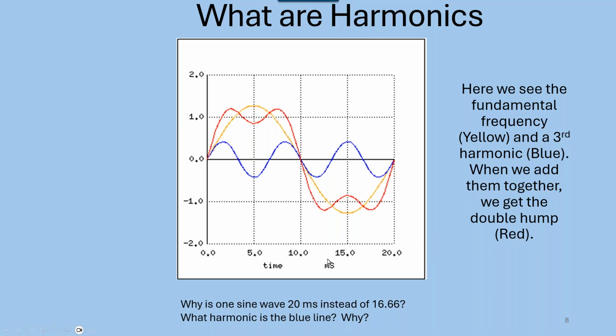Since we've got harmonics and I've got the fundamental, when you add these together, you get this distorted waveform. You see how this is positive and this is positive, so that puts it way up here. If I go to this peak of the fundamental, it's here, this one's negative, so it actually brings it down. So when we get into harmonics, this is why we get all these distorted waveforms, because we're combining all these different harmonics. Okay?